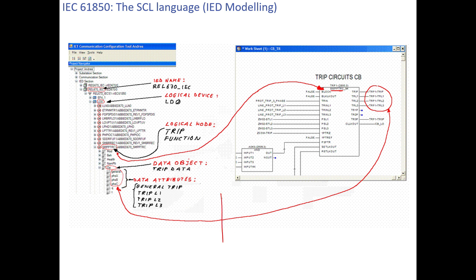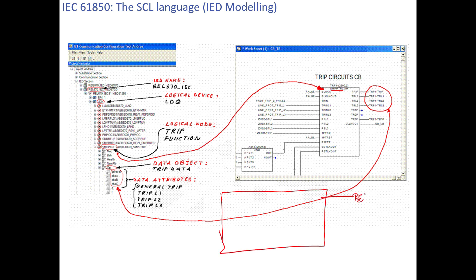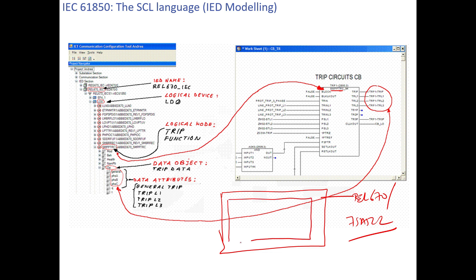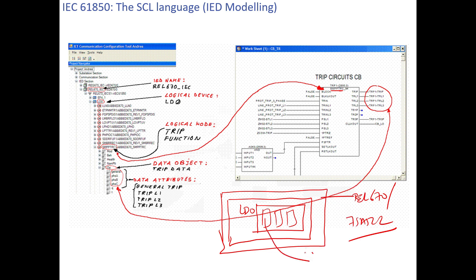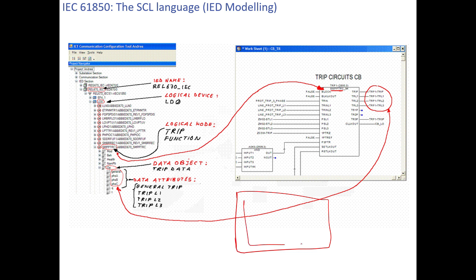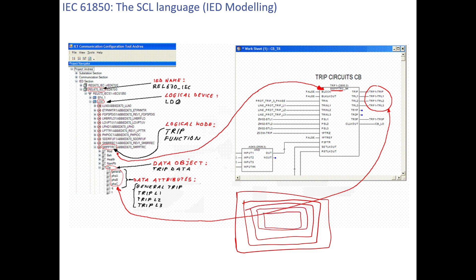In summary: if you have a physical device like REL670 or 7SA522, inside that device there are logical devices. One logical device is LD0. Inside LD0 there are many logical nodes such as SMPTRC or PDIS. Inside each logical node there are data objects, and inside each data object there are data attributes. So the hierarchy is: physical device → logical device → logical nodes → data objects → data attributes.